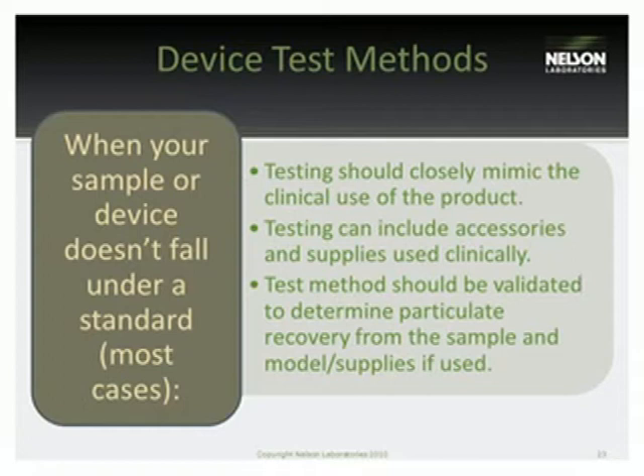But ultimately, testing of any device, when testing for particulate matter, should closely mimic the clinical use of the product. This has been recommended by most regulatory agencies and is also recommended by the TIR document. Testing should also include accessories and supplies used clinically. The purpose of this is to see if there's any sloughing or interaction between those accessory devices and the test device. The test method should also be validated in most cases to determine if the particulate recovery from the sample and any model or supplies that are used is adequate.